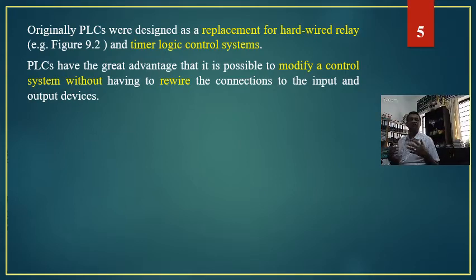Now what if we want to change this particular process to A plus, B plus, C plus, then A minus, B minus, C minus? If we have to switch over to this process, the first essential thing is that all these valves, relays and cylinders need to be recircuited in order to get the required operation A plus, B plus, C plus, A minus, B minus, C minus. That is the biggest hurdle of any relay system used in the industry.